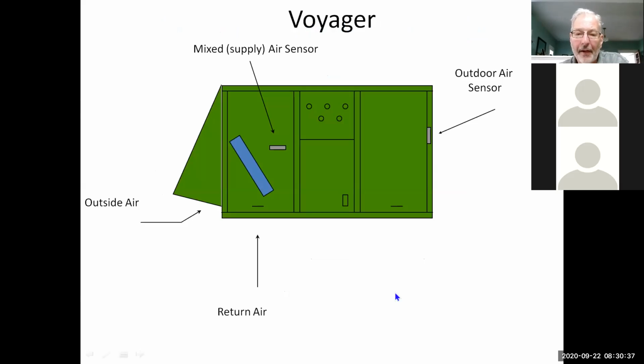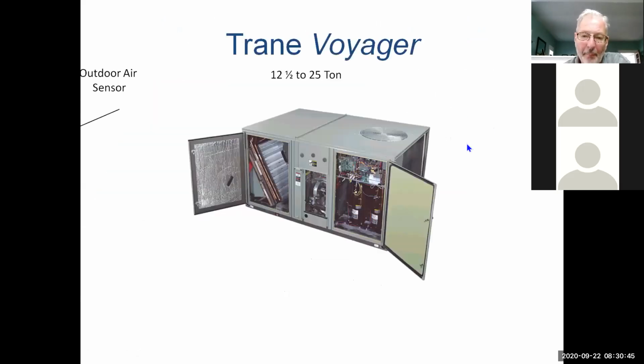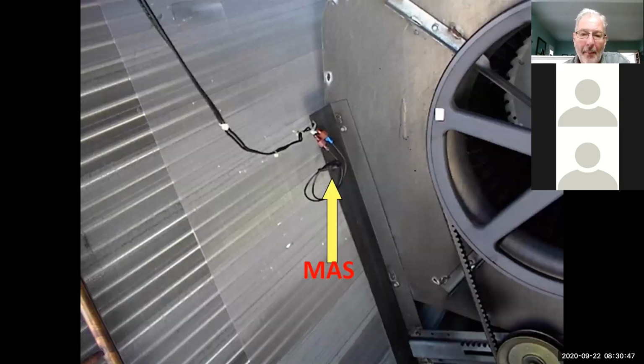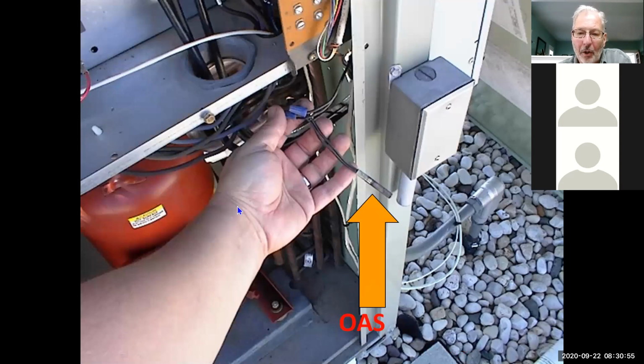Where are the controls on here? The mixed air sensor is in the blower compartment. The outdoor sensor is in a couple different places. We'll talk about those in a minute. But the mixed air sensor, on some of the older units, there's actually a grommet in the back of the blower housing that it sticks in. Most of the newer ones are just clipped to the blower.